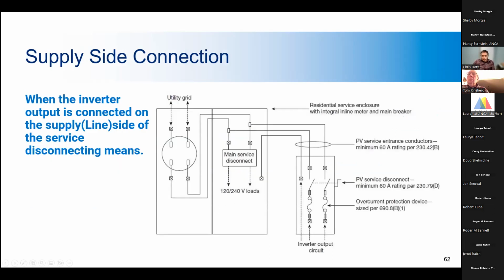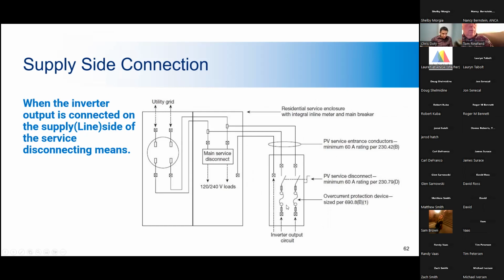All right, so the other type of interconnection is a supply side connection. This is when the inverter output is connected on the utility side of the main service disconnect. This is also referred to as a line side connection or a line side tap.